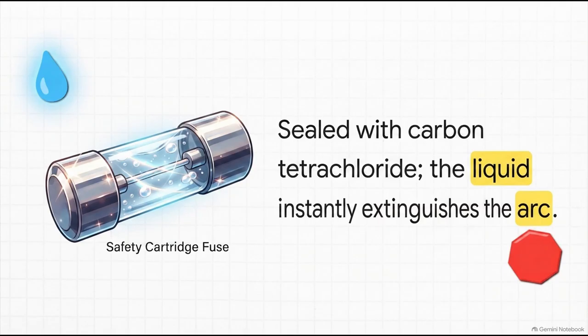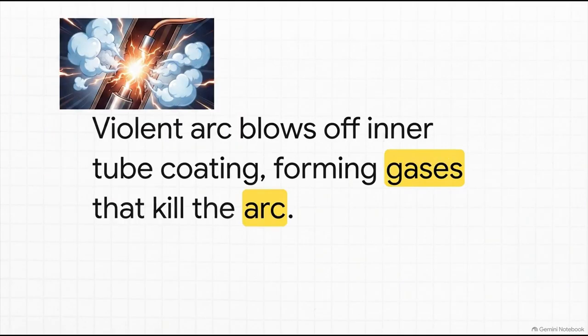These tubes are sealed tight at both ends and completely filled up with carbon tetrachloride. You see these heavily employed for transformer protection or backing up circuit breakers. When a fault occurs and that safe limit is exceeded, the fuse element blows out. But watch what happens. Instantly, the carbon tetrachloride liquid itself becomes the arc extinguishing medium. It is actively battling and killing the electrical arc right inside the liquid tube. And finally, we have the big one, the explosive, self-sacrificing expulsion-type high-voltage fuse.